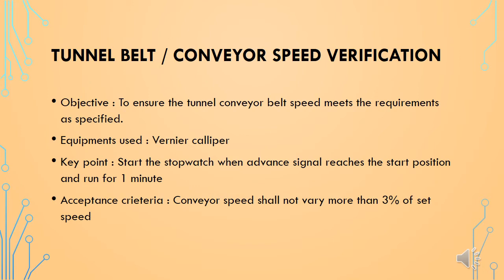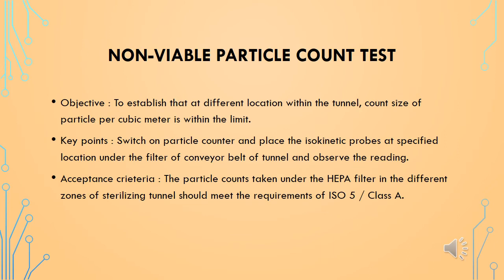The third qualification test is tunnel belt or conveyor speed verification. This test is performed to ensure the tunnel conveyor belt speed meets the required specified conditions. To perform this test, we need a vernier caliper and stopwatch. In the procedure, start the stopwatch when the advance signal reaches the start position and run for one minute. The acceptance criteria is that conveyor speed shall not vary more than three percent of the set speed.